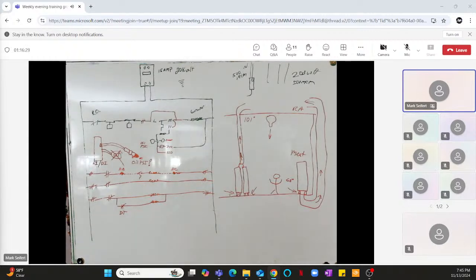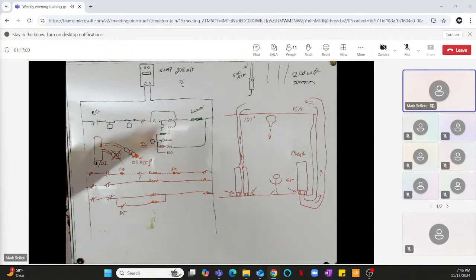It is nice to be able to reset it easily like that. It's nice also that you don't have a lot of this other stuff in here. Personally, I'm old school, obviously. I like this other stuff built in. It really does away with a 3-wire old school oil fail control. Everything down here can trip, and it's not going to trip on oil fail. The only thing that'll trip on oil fail is the trip breaker for the main. And everybody knows if you've got a trip breaker for the main on the compressor, you're almost always going to have a tripped oil fail. So that's how it works. It's just through software, and it's nothing more than that.